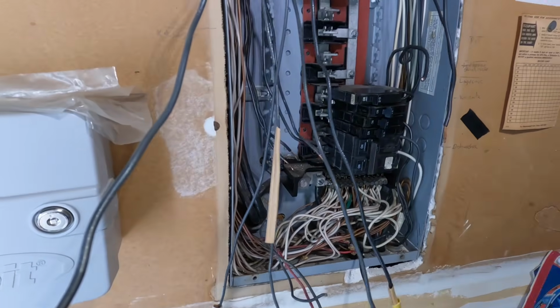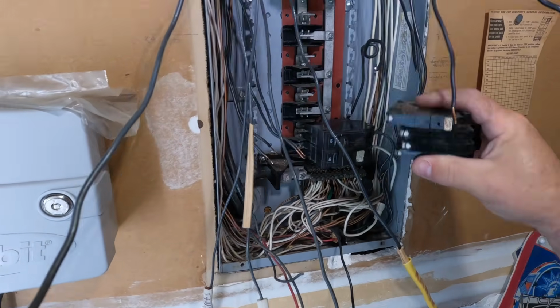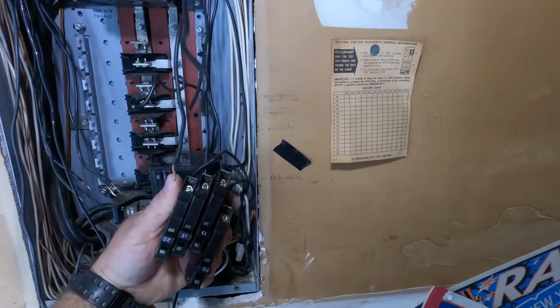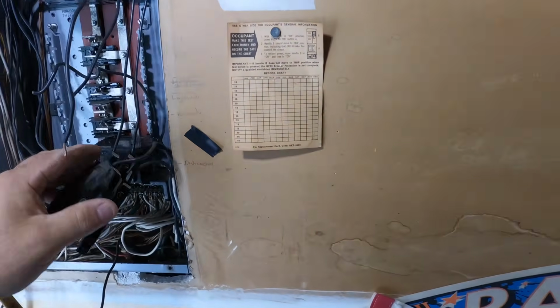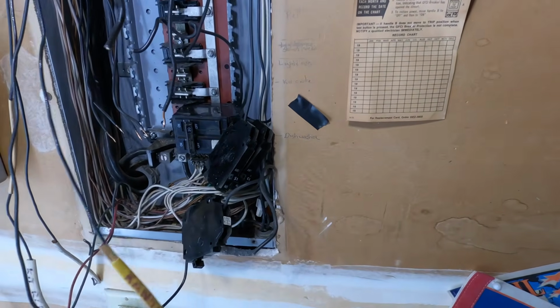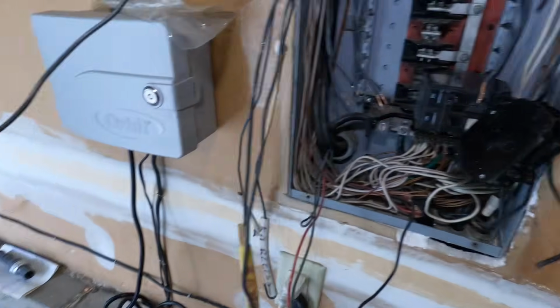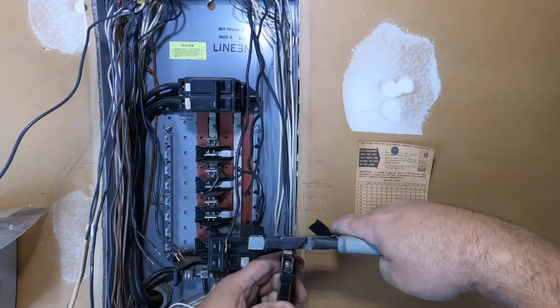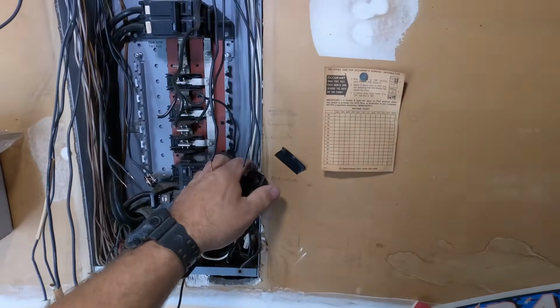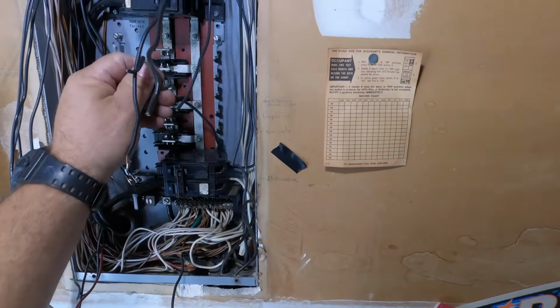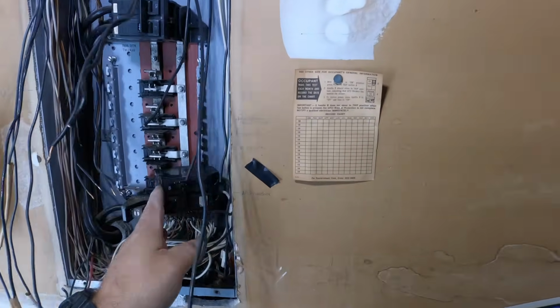You can't have a circuit breaker higher than 6 feet 6 inches. So when I work in an area like this, I usually mark where 78 inches is, 6 feet 6 inches, in pencil on the wall, so I know my main breaker can't be higher than that. And not just the main breaker, but any individual breaker cannot be higher than 6 feet 6 inches. That's what the code says.